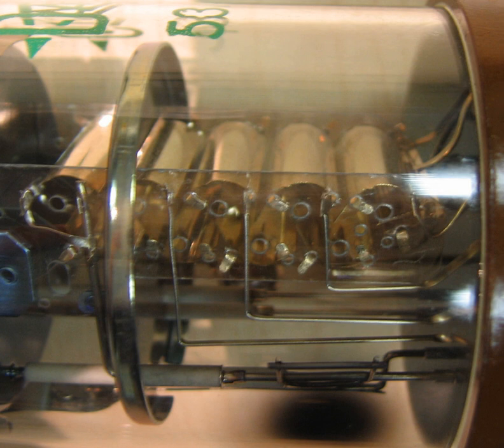The necessary distribution of voltage along the series of dynodes is created by a voltage divider chain, as illustrated in Fig.2. In the example, the photocathode is held at a negative high voltage of order 1000 volts, while the anode is very close to ground potential. The capacitors across the final few dynodes act as local reservoirs of charge to help maintain the voltage on the dynodes while electron avalanches propagate through the tube.